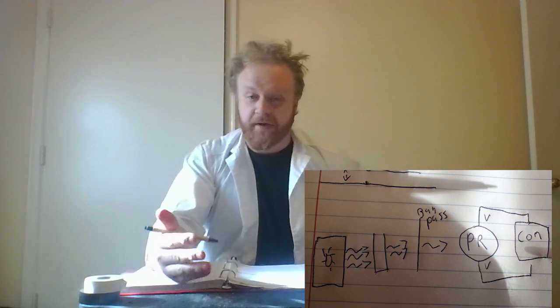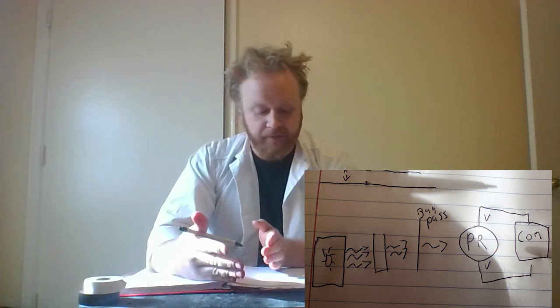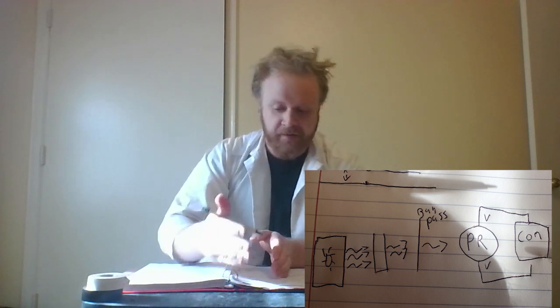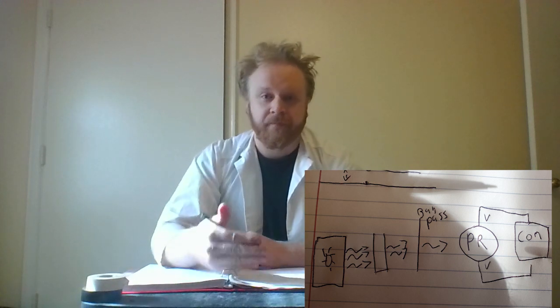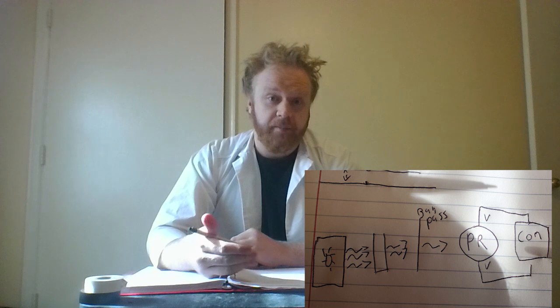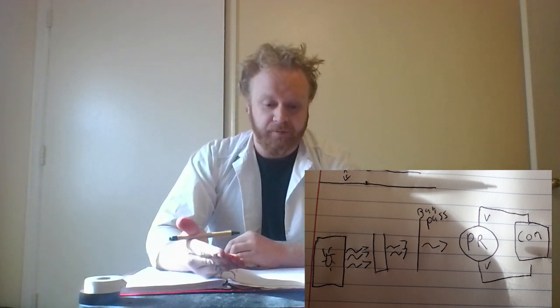And that can either display the voltage, and then you can apply your own calculations for your blank or your initial light and your final light or your transmitted light. Or, in my case, you can program the computer to do it for you and display the result as an absorbance.